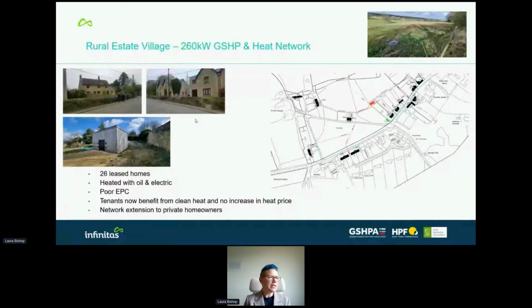One of the things we're now looking at doing is connecting some of the private homeowners in the village. The energy centre was actually oversized to start with, and the ground collector was oversized to allow more people to connect on, so that's something we're looking at. We're also looking at connecting up a solar array they've got nearby to offset some electricity running costs of the heat pump, and at increased thermal storage so that we can do some demand shifting.